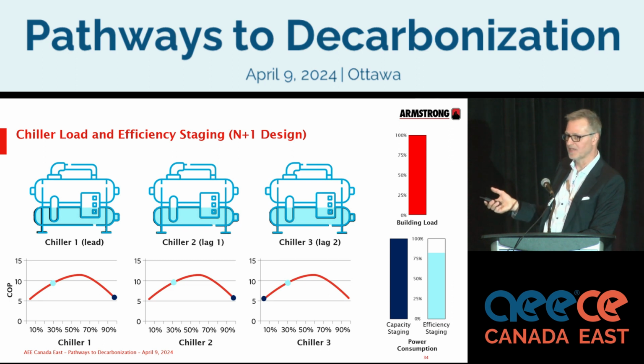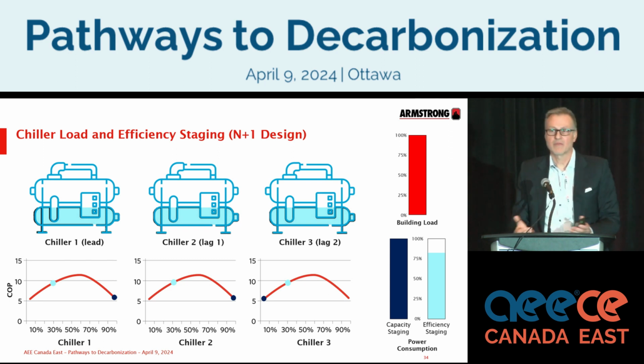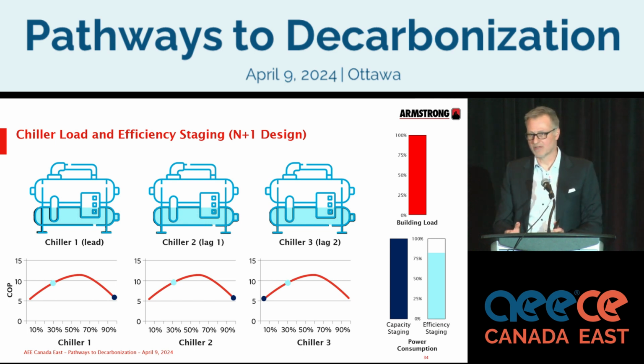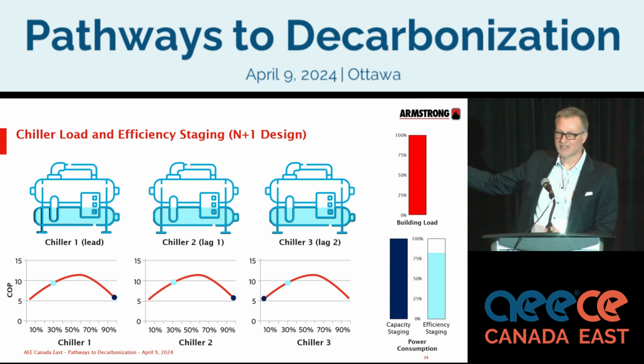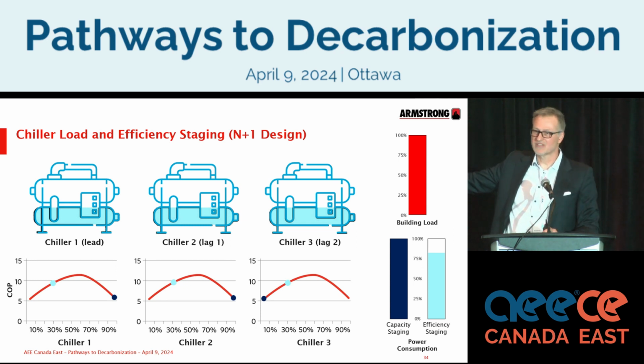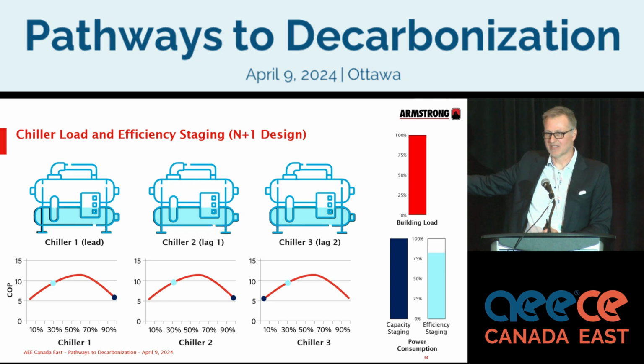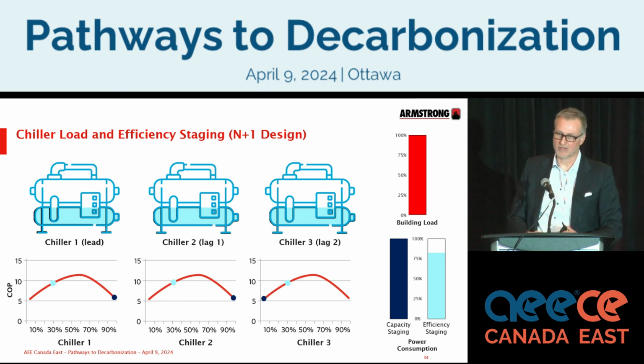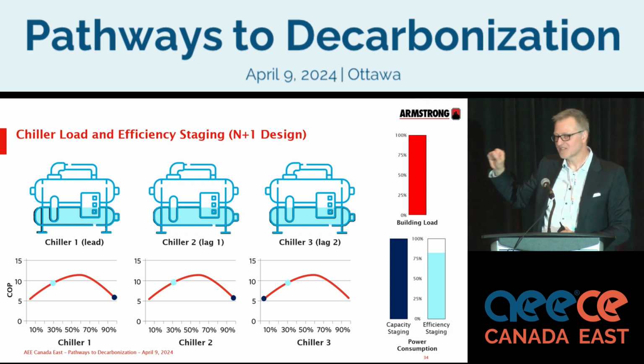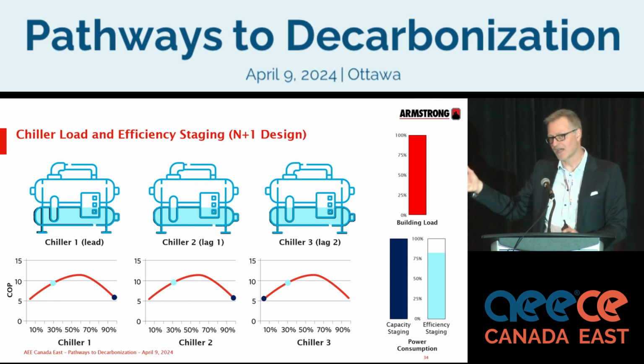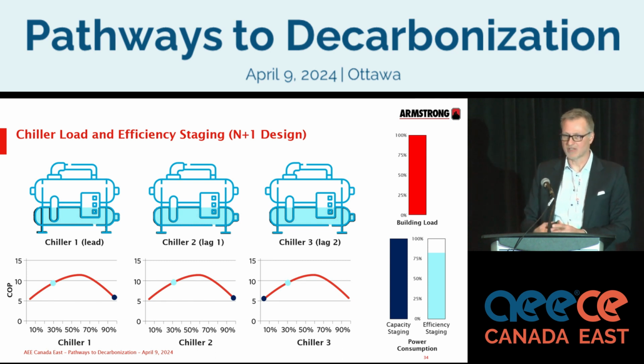I'm improving my COP. And the logic here is, remember, what are we doing with our chillers? We're moving thermal energy. All we've done in this is utilize the surface area we have sitting in that idle asset. More surface area, unloading the chiller a little bit. The key here then is that there's significant energy savings opportunity, especially on design day considerations, on peak load, where if you look at the data set that's provided, you can save up to 10% on your energy consumption on your chillers on that design day if you have redundancy in your equipment or an N+1 consideration.